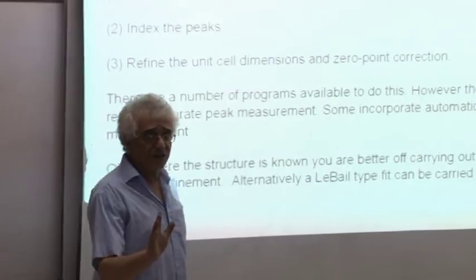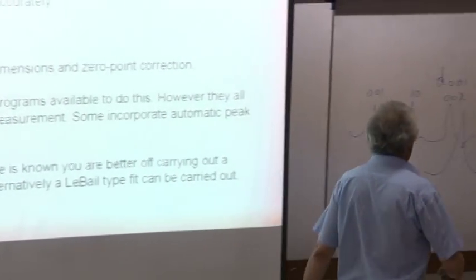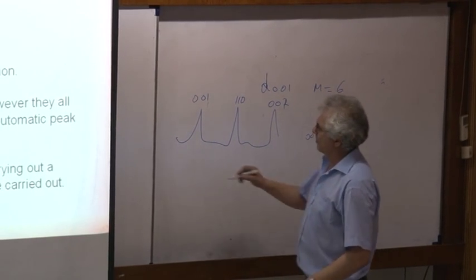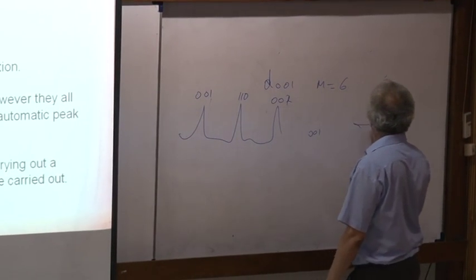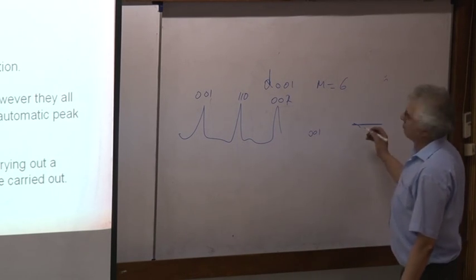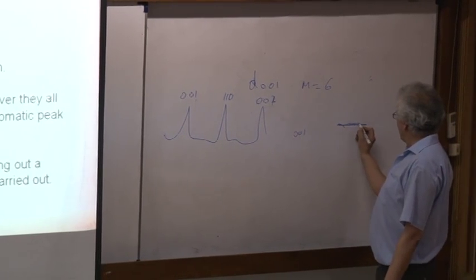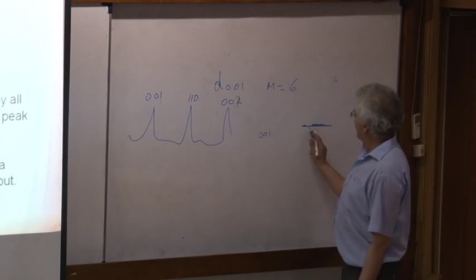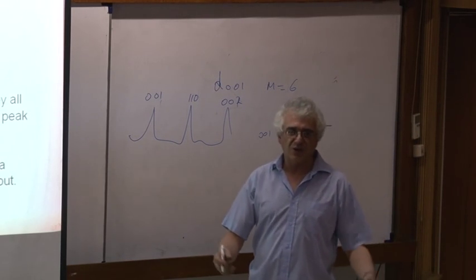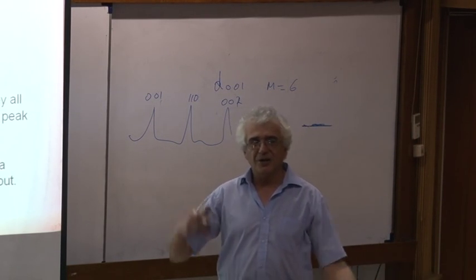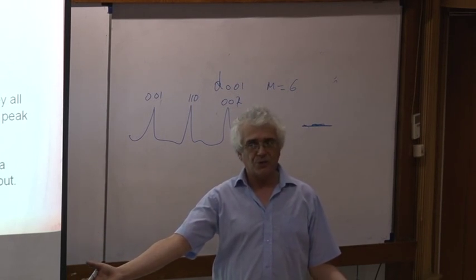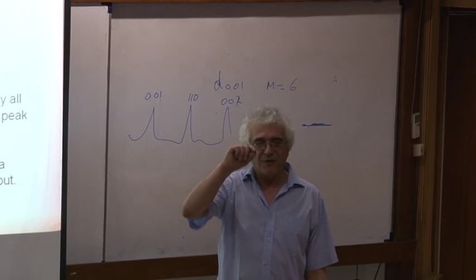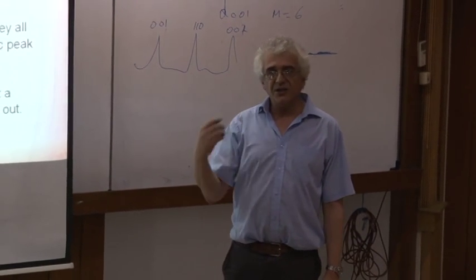Okay, now what is the 0-point correction? Every time you put a sample onto the diffractometer, you might have a slightly different height of your sample. You might have a thicker sample, thinner sample. You might find that in between changing the diffractometer from doing high temperature work to doing standard room temperature work, you are a micron in difference in height. Okay, this is accounted for.